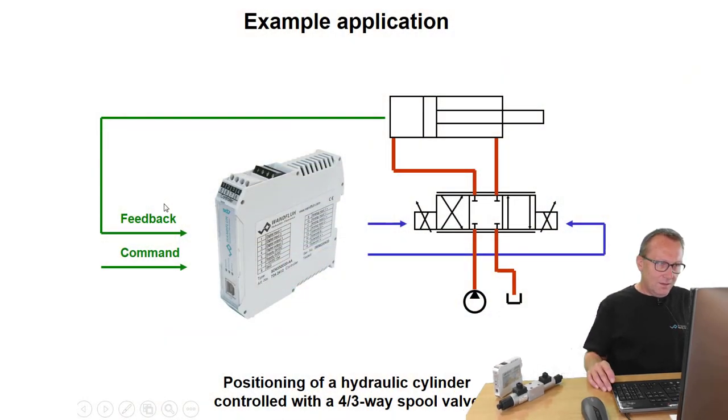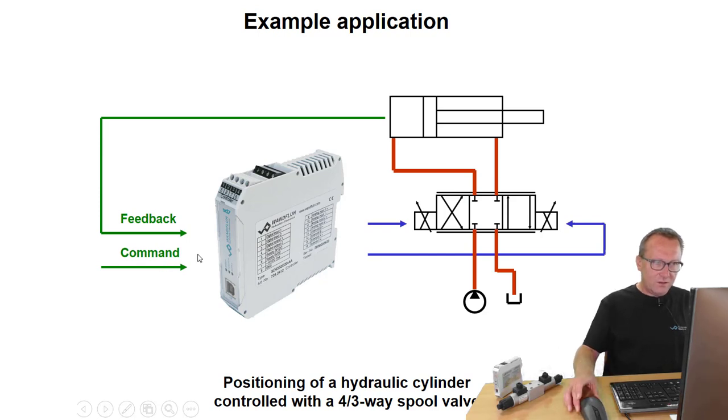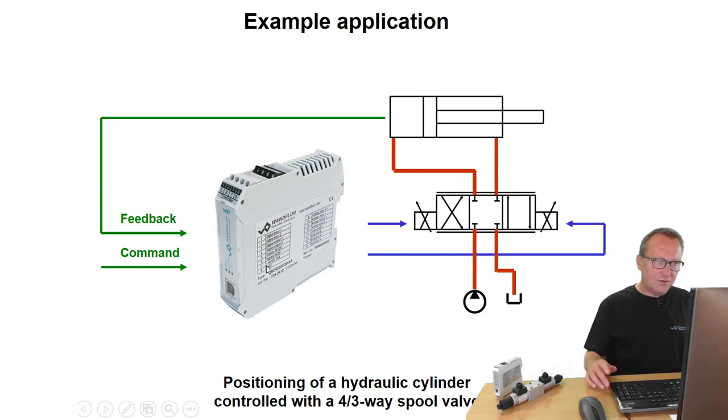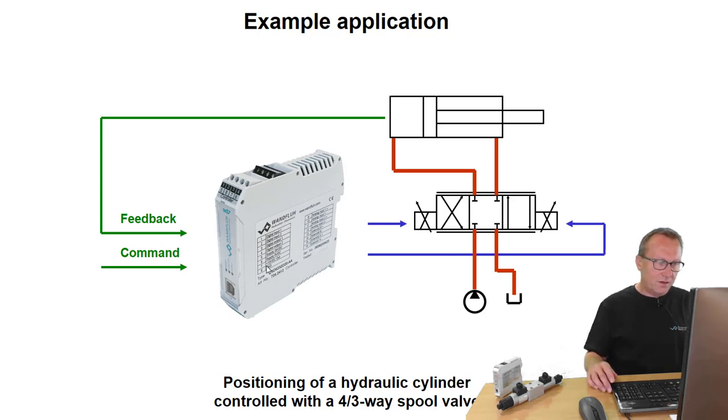The difference between the open loop and the closed loop system is the feedback signal. This feedback signal is compared to the command value inside the electronic card, and if there is a deviation between these two signals, the card will readjust until the feedback and the command value are identical.